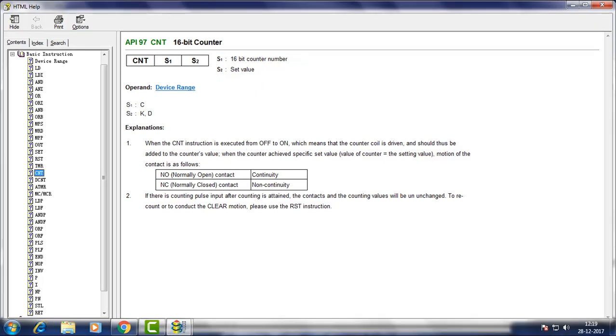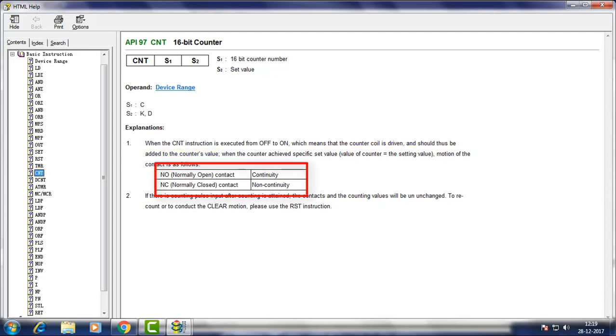The explanation says whenever the counter coil is driven, the counter's value is incremented by 1. When counter value reaches preset value, the NO contact gives continuity and NC opens. And counter stops counting after reaching preset value.